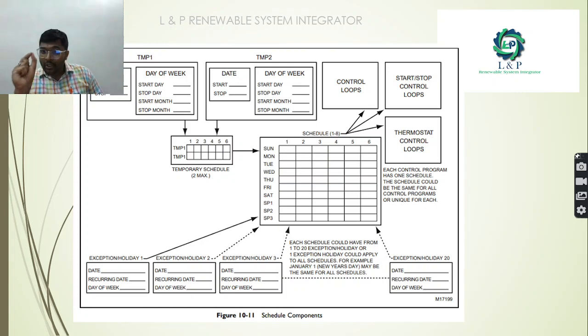So each control program has one schedule, okay. The schedule could be the same for all the control programs or unique for each. So it is up to us to create a schedule for each and every program that we are planning, okay. If you have a common calendar block, it will be a typical and common program for everything, and most importantly, even for the control loops, the start and stop of a control loop, you can schedule, okay.